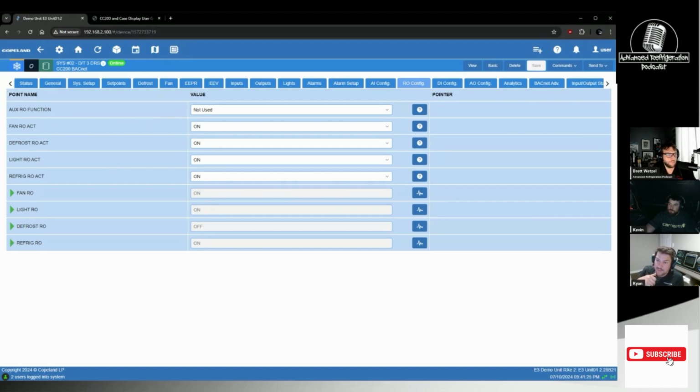MSTP being Master Slave Token Pass. That's a whole episode on talking about BACnet and troubleshooting and all that stuff. Otherwise, we can also get them under Modbus. Myself, I'll choose BACnet IP any day. It's a lot easier, in my opinion, to troubleshoot a network when it's IP based. You just have a Cat5 checker and put one into the other. Yeah, you're good. So let's talk about that for a second.